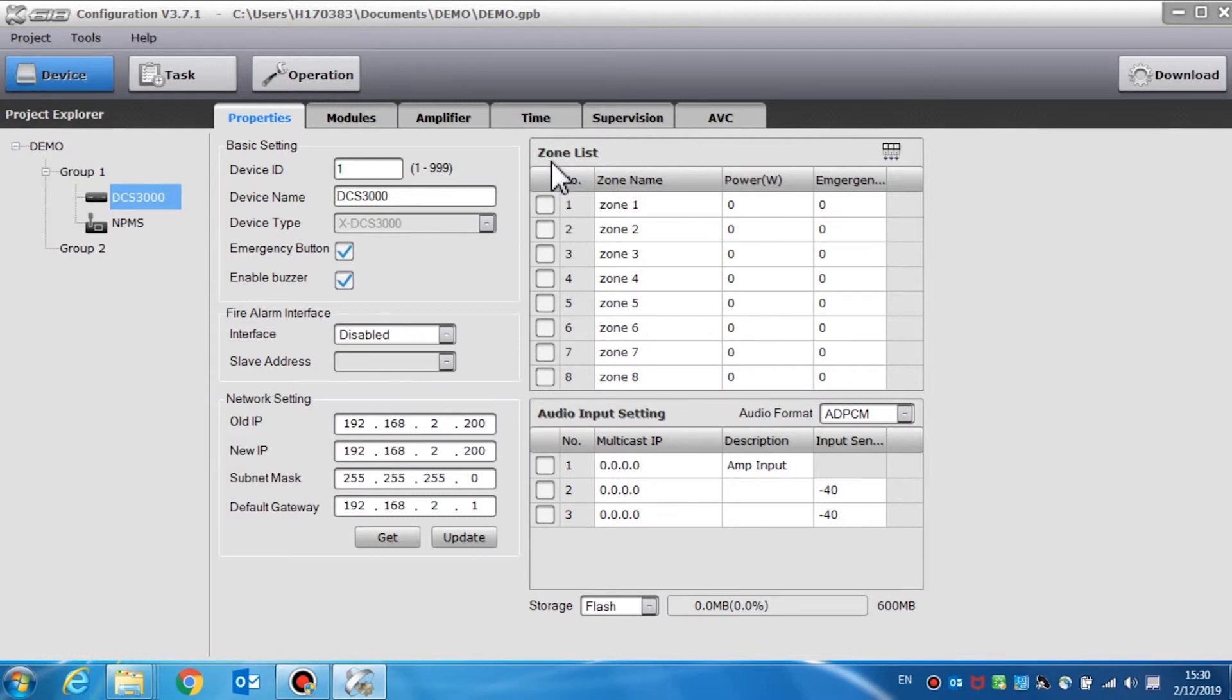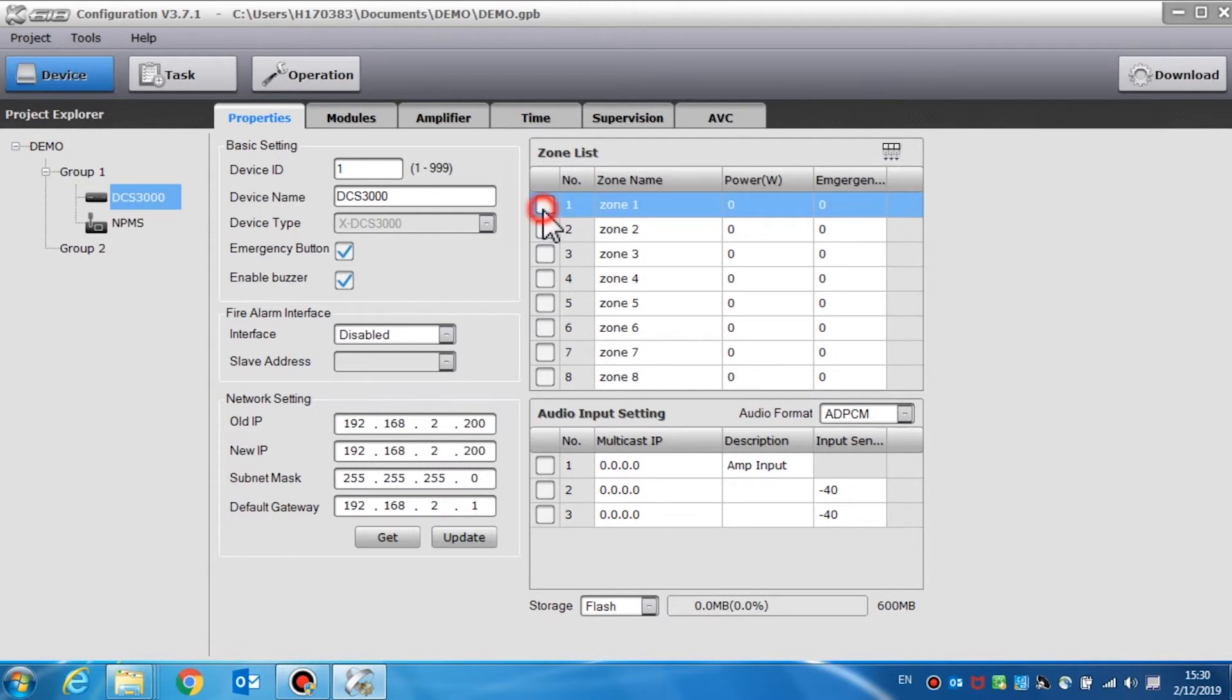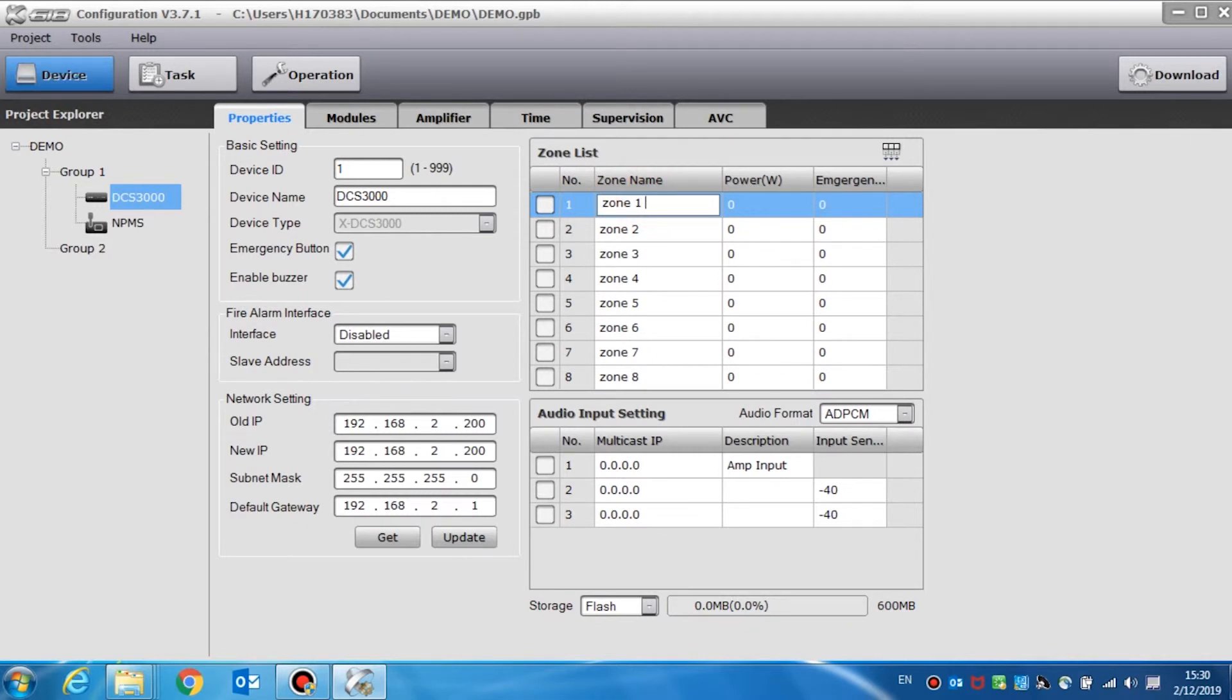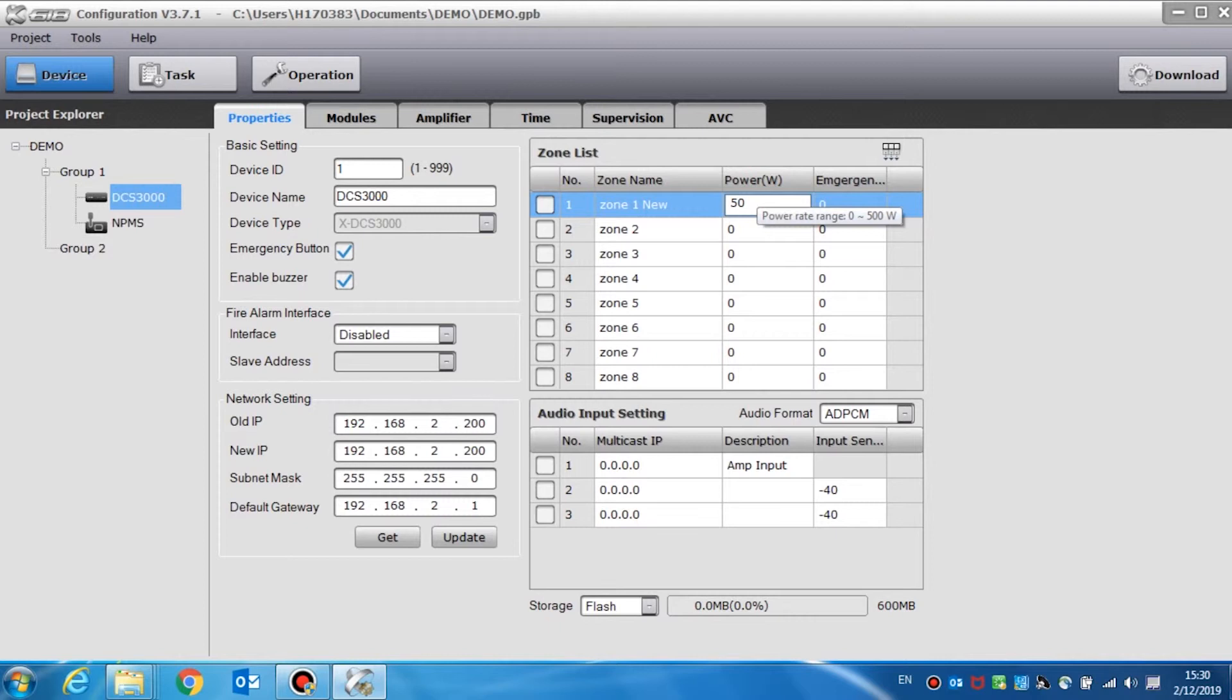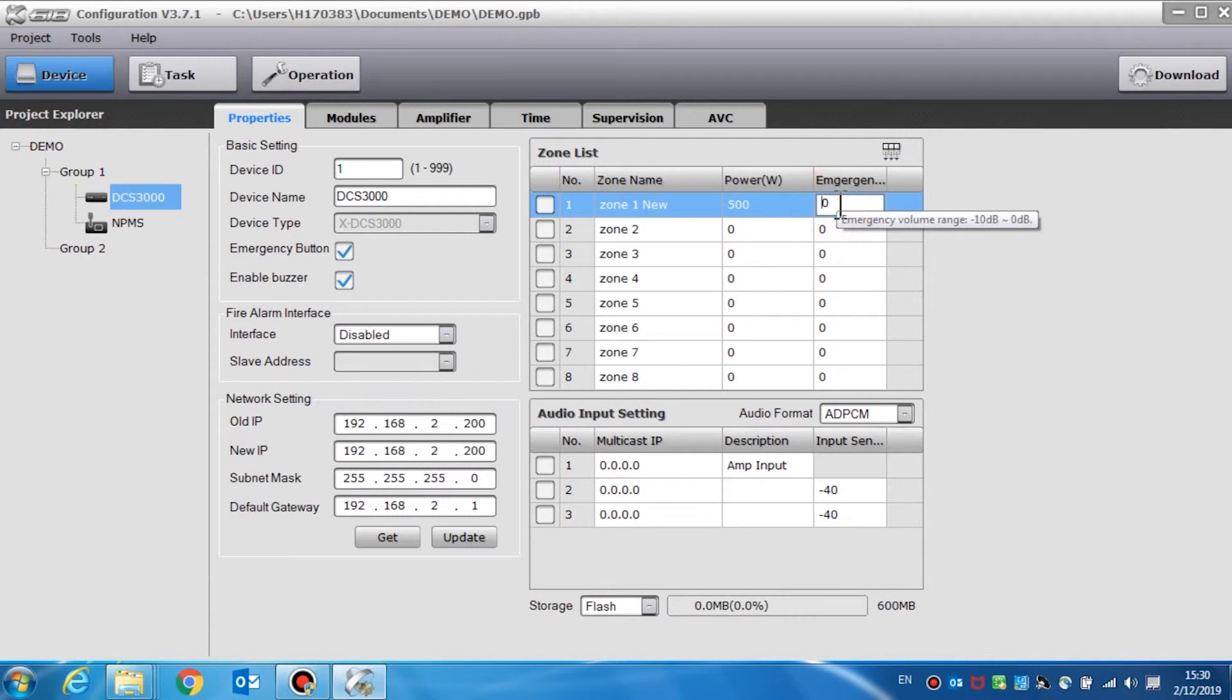The zone list setting allows users to enable or disable the zones and add the description of the zone name and power. Select the checkbox to enable the corresponding zone. Click the zone name or the power to edit it. The power setting value is only used to determine if the amplifiers are appropriate. The emergency volume of each loudspeaker line can be set and the ranges are from negative 10 decibel to zero decibel.